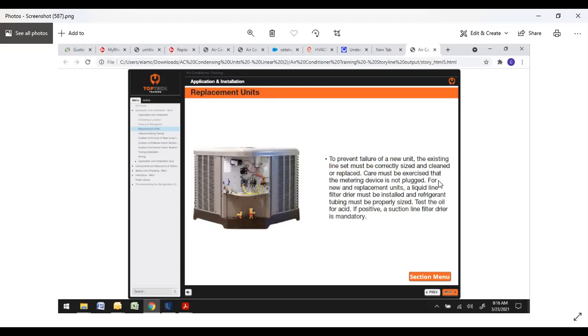So for new and replacement units, a liquid line dryer must be installed and refrigerant tubing must be properly sized. They provide the filter dryer with the unit. It's up to you whether you put it at the outside or the inside. People will argue both ways. Mainly you want to just make sure that it's included, and anytime that you open the system up, that it's replaced.